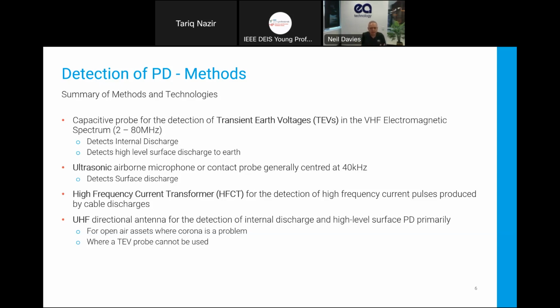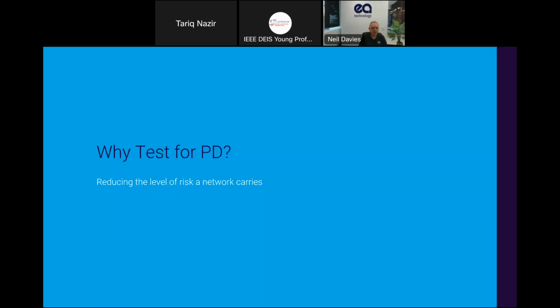So that's really the background that I want to talk about. But today, my focus is more on: why are we testing, and when will it fail? So we test for partial discharge, and electricity companies, any high voltage user, will use PD testing or other condition monitoring to reduce the level of risk that any network carries. It's all about risk management at the end.